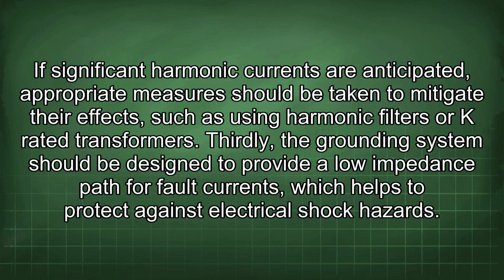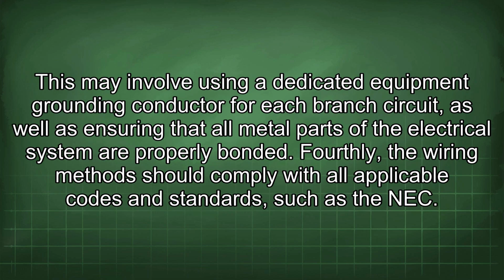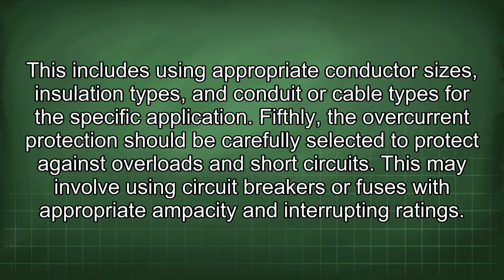or K-rated transformers. Thirdly, the grounding system should be designed to provide a low impedance path for fault currents, which helps to protect against electrical shock hazards. This may involve using a dedicated equipment grounding conductor for each branch circuit, as well as ensuring that all metal parts of the electrical system are properly bonded. Fourthly, the wiring method should comply with all applicable codes and standards, such as the NEC. This includes using appropriate conductor sizes, insulation types, and conduit or cable types for the specific application.